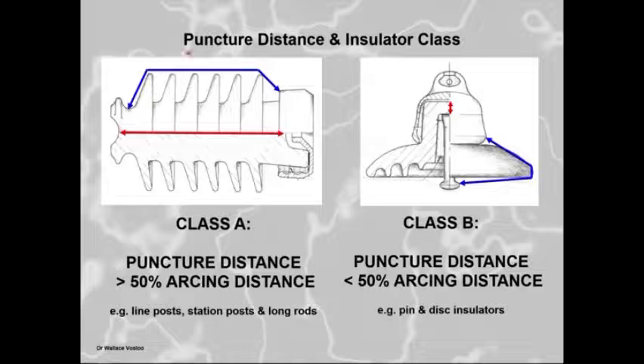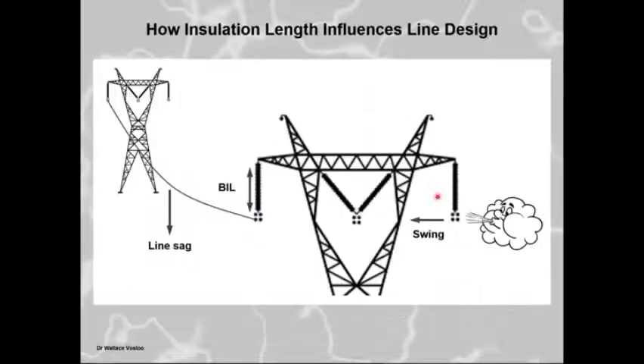If we go on, we've got something which is called the puncture distance, and the insulator class is determined by this puncture distance. Now for a class A type insulator, you find that the puncture distance, this red line here, is larger than 50% of your arcing distance. So if this is larger than 50% of that, it's a class A. If it's smaller than 50% of that, then it's a class B. So you can see class B is a type of insulator which could be very prone to puncturing. Class A would rather flash over the surface than puncture. And that's the difference between class A and class B insulators.